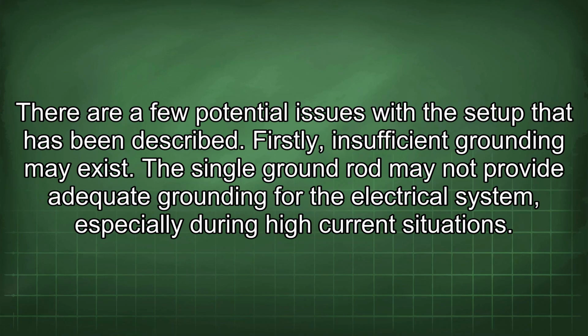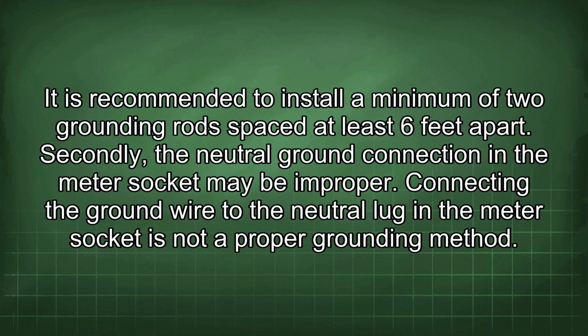There are a few potential issues with the setup that has been described. Firstly, insufficient grounding may exist. The single ground rod may not provide adequate grounding for the electrical system, especially during high current situations. It is recommended to install a minimum of 2 grounding rods spaced at least 6 feet apart.